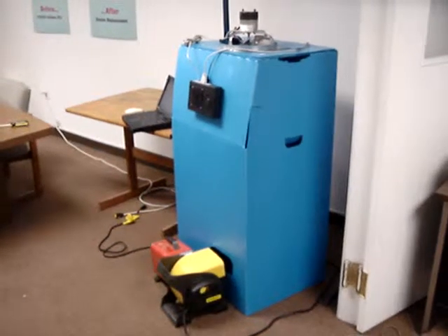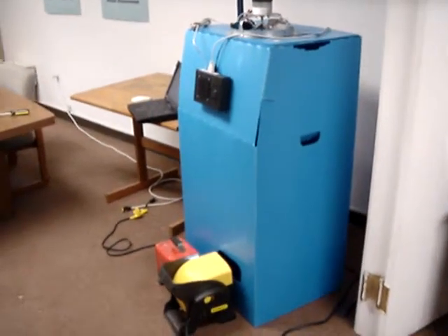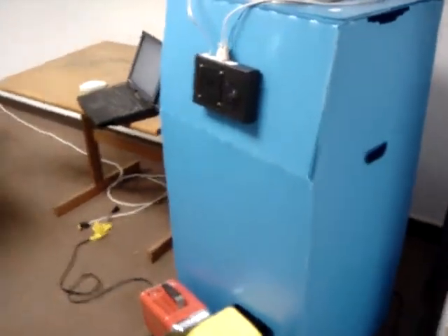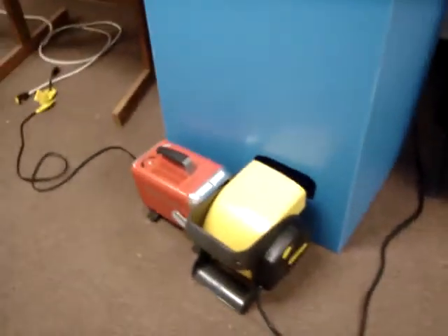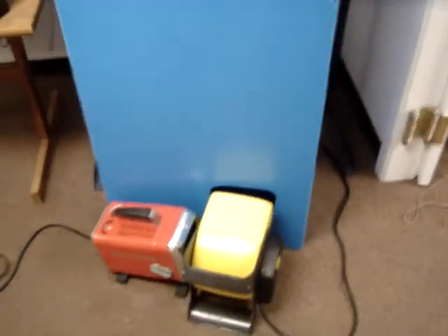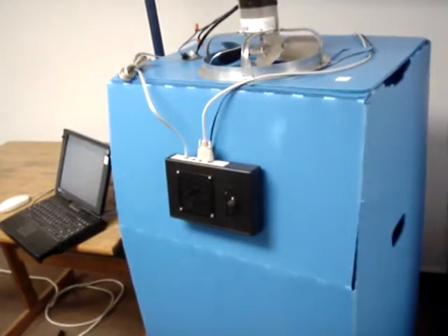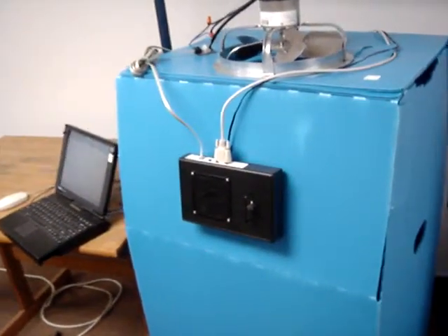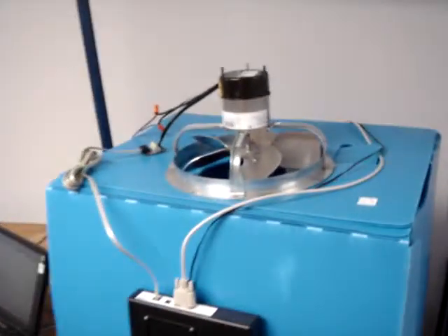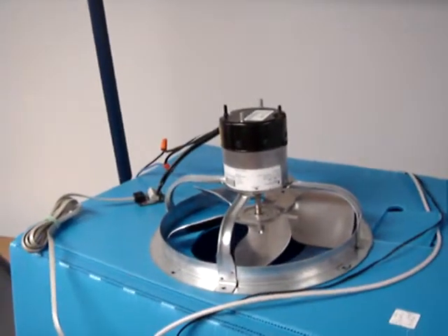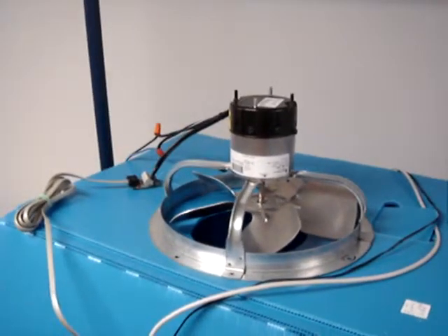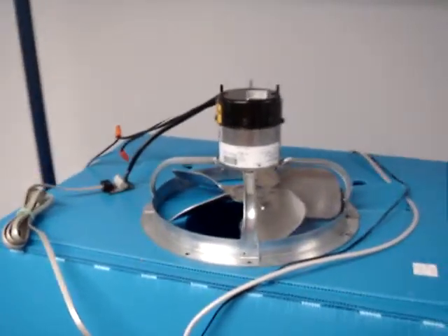So this is the setup we're using to demonstrate the CFM matching technique. We have a box that's simulating a server rack, and we have a red heater and a yellow fan here at the bottom that simulates servers blowing hot air into the server rack, which are the heat loads. And then we have the CFM sensor itself here on the front. And on the top we have an electrically commutated fan, and that's the exhaust fan that's going to be exhausting the hot air that's being blown in by the servers.